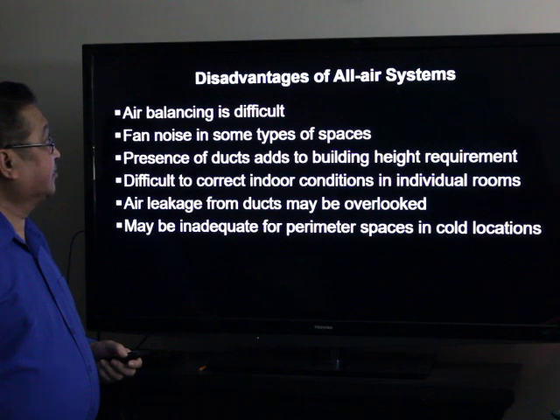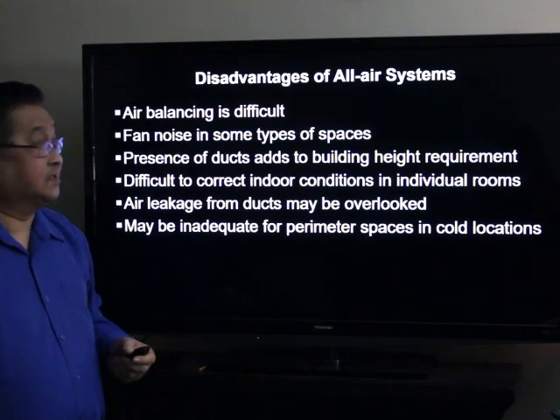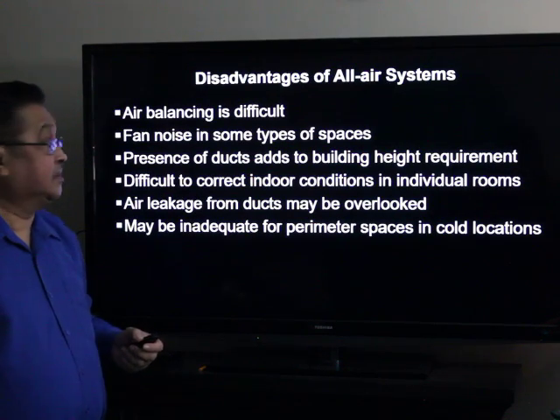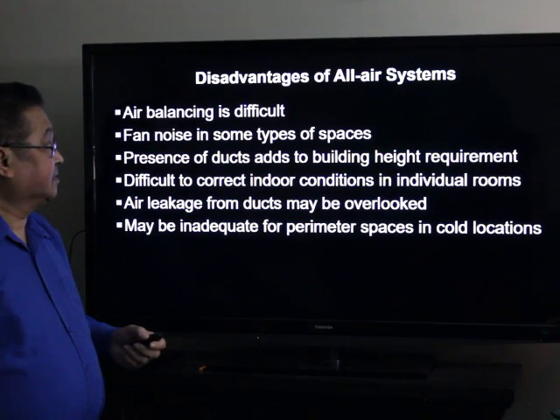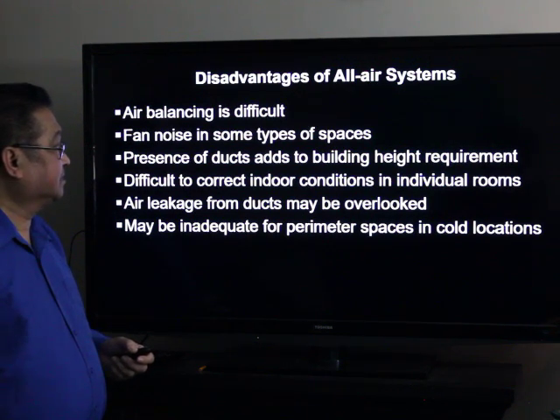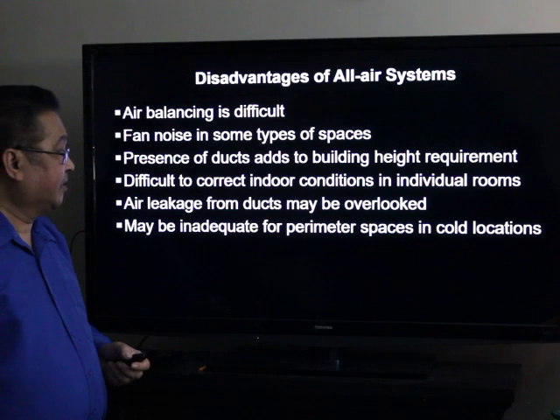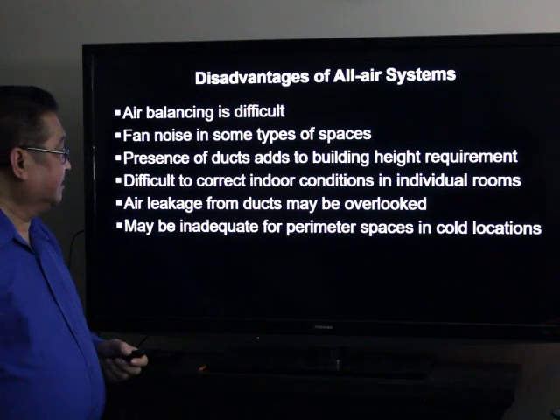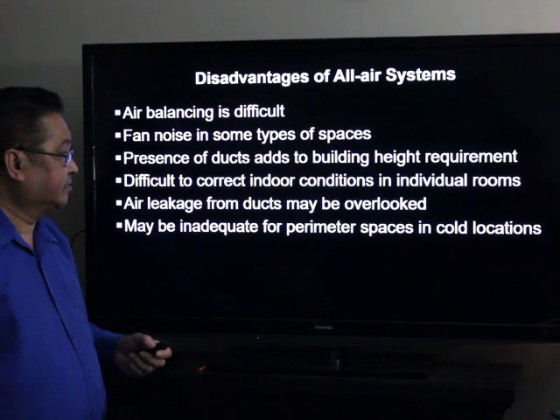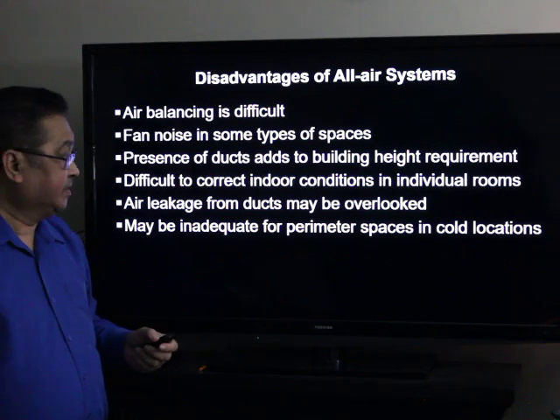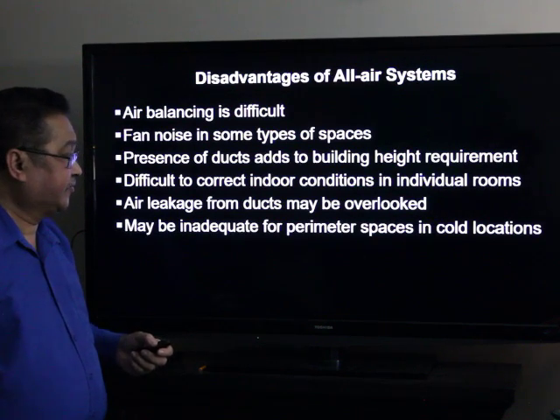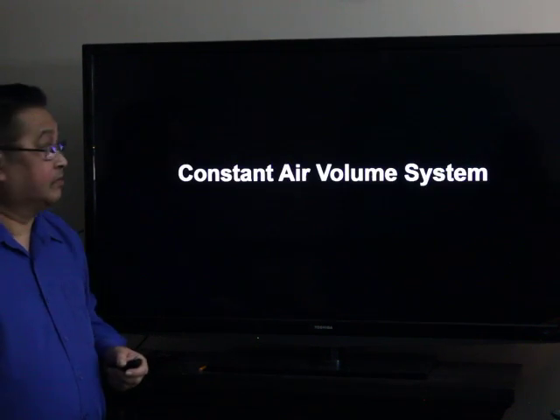Disadvantages of all air systems: air balancing is difficult, and fan noise is noticed in some types of spaces. The duct presence adds to building height requirements, and it is difficult to correct indoor conditions in individual rooms. Duct leaks may be overlooked, and sometimes it is inadequate for perimeter spaces in cold locations.